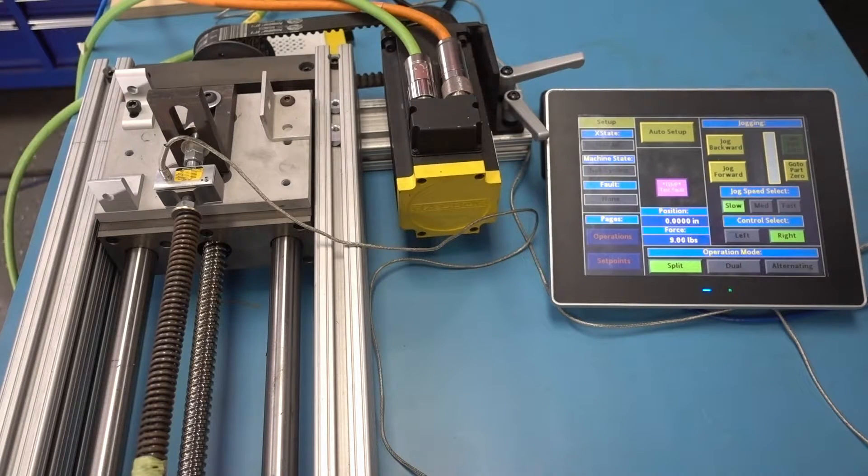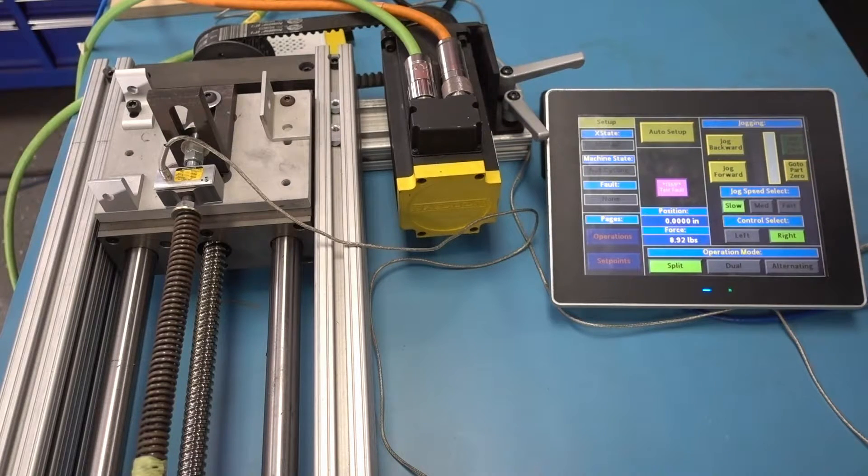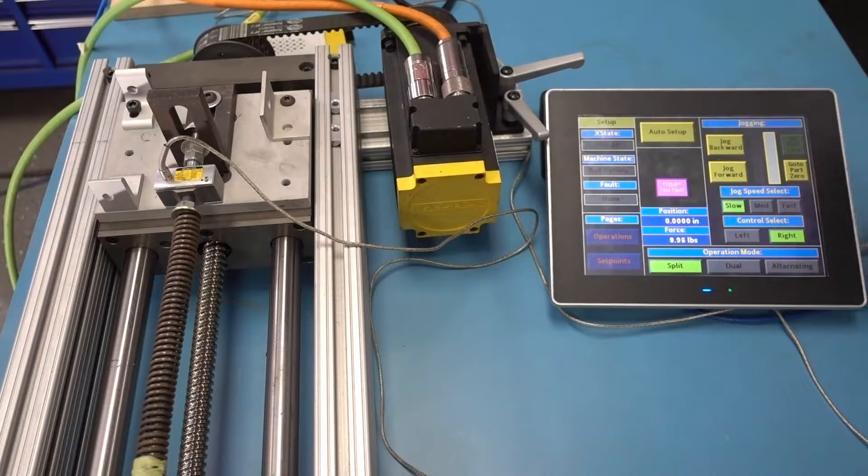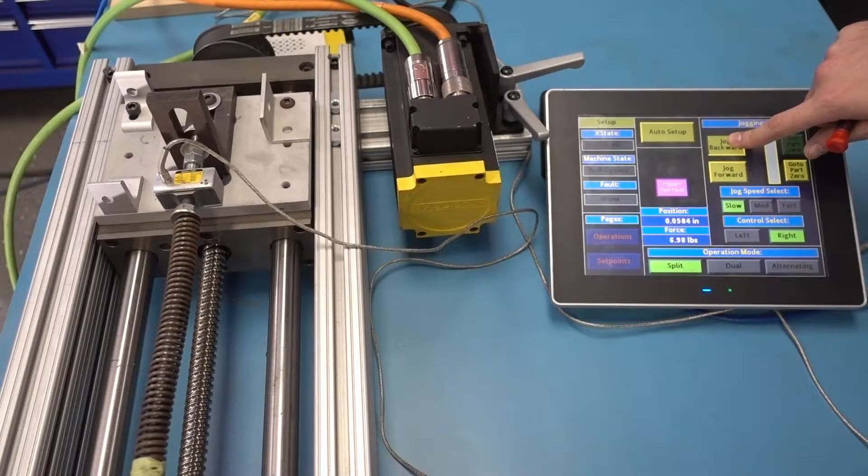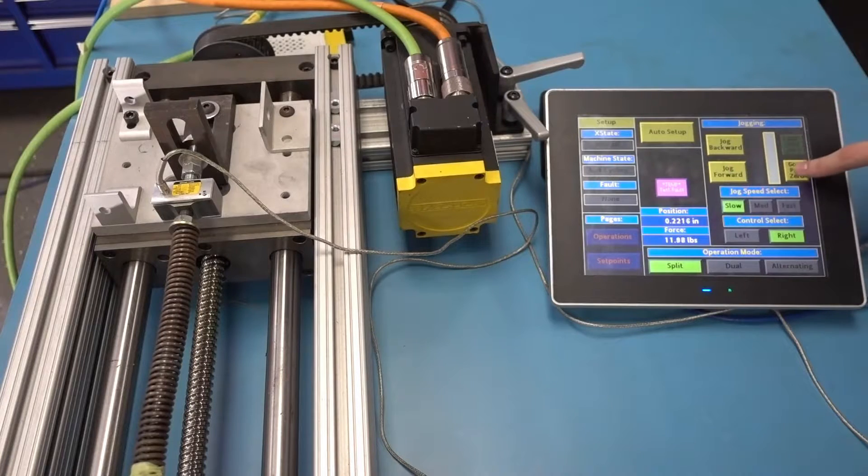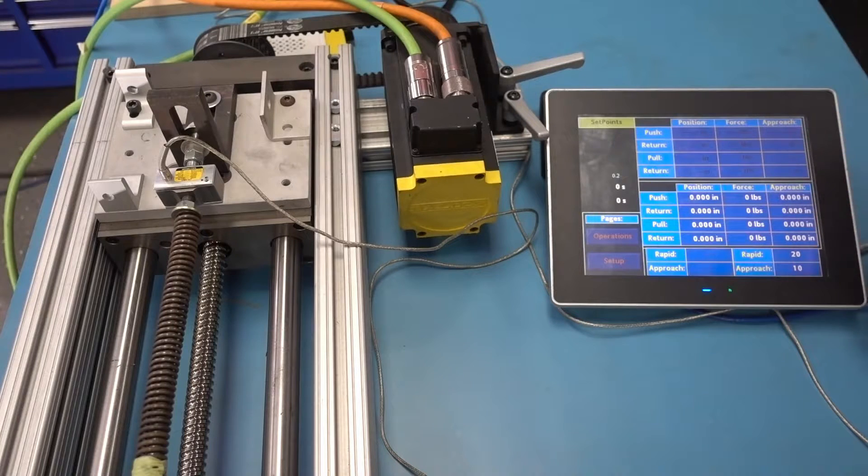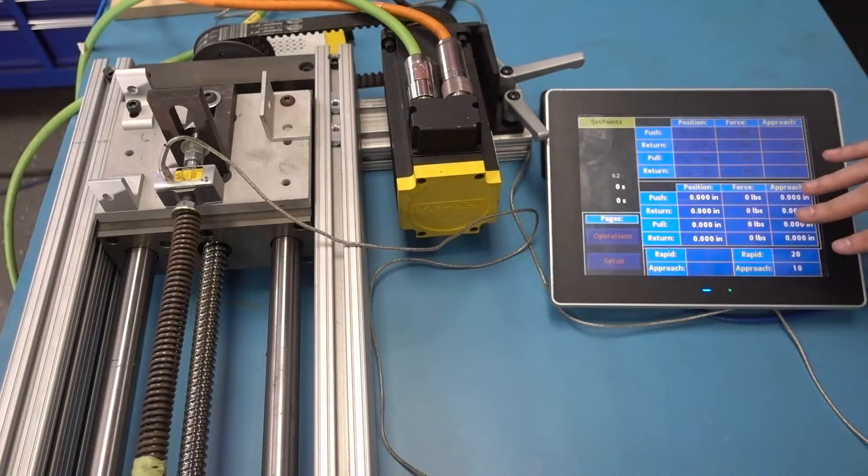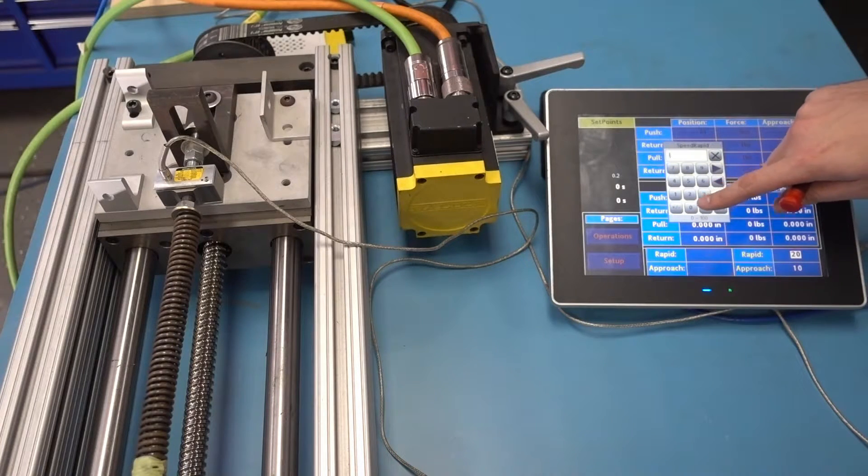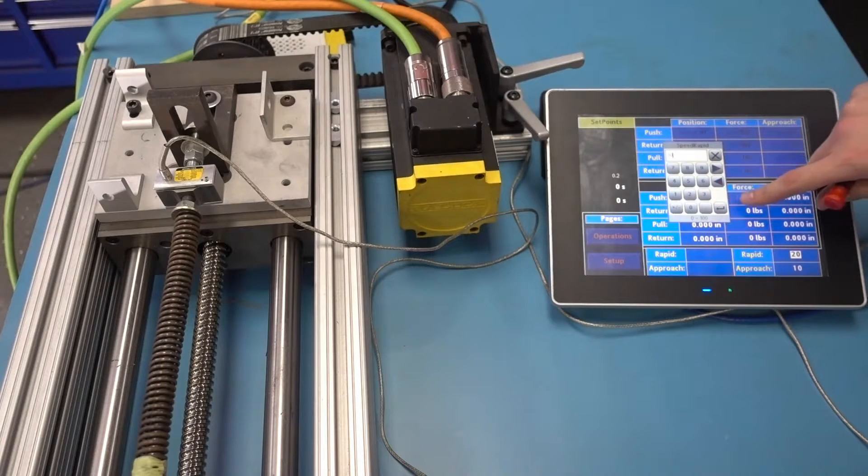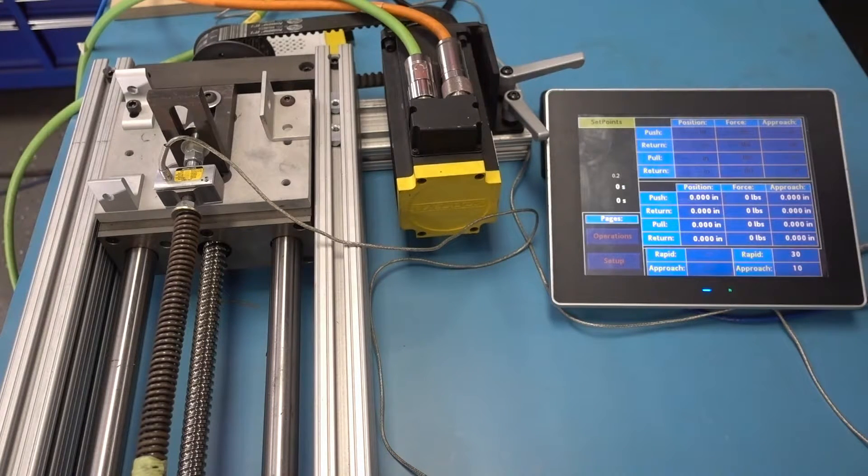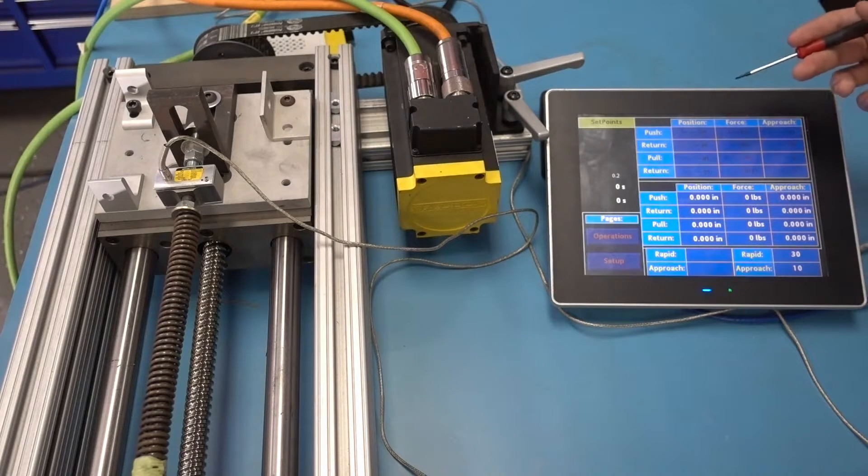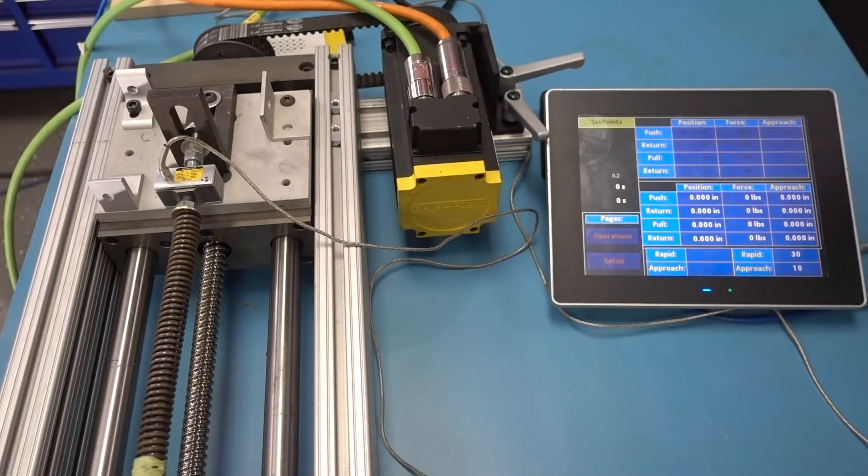So HMIs are used to set settings, view the state of the machine, sometimes it's used to jog the machine, depending on safety requirements and stuff. Here you can see I can move the axis around like this, and you can give it commands. So you can see if I switch over to a setpoints page, you've just got a giant page full of settings, and these values are actually in the drive I showed you earlier. So when I change this value here to 30, then that's a speed setting, it'll actually go faster now, because that value has changed in the drive. And that's the value of an HMI, it is just an interface for whatever controllers or drives or anything that you have on the system.